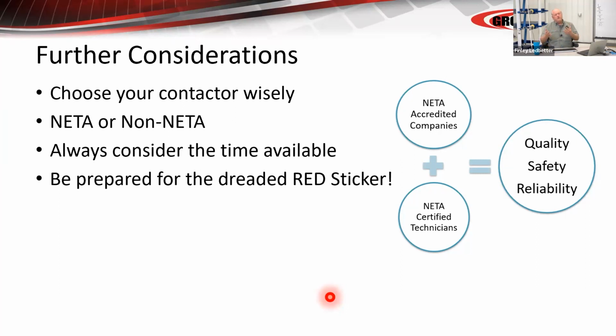And if there's not a workaround and they want to re-energize it, make sure you get them to sign off in writing that you're turning a circuit back on that you're recommending they not do, because you will see that. They will promise you they will replace it, and you'll come back in 5 years and that cable will still be in service and the results will be way worse. It'll be way hot and they will have jumpered all kinds of circuits around it. So be prepared for the red sticker.